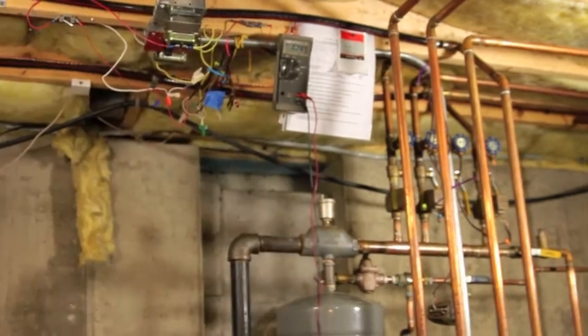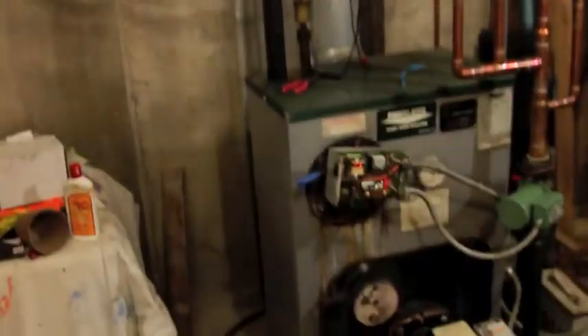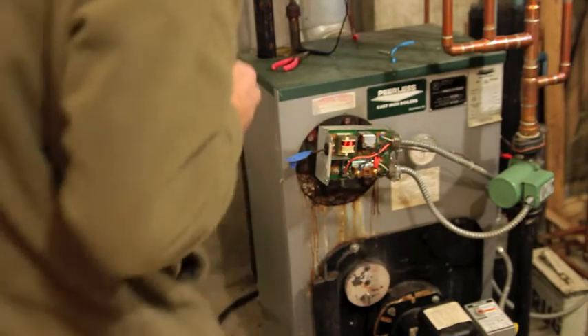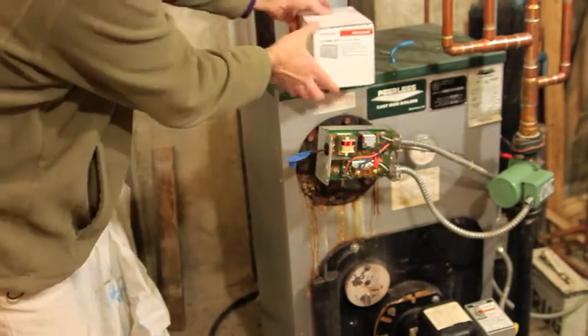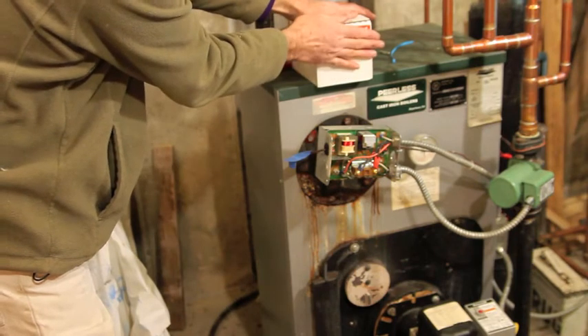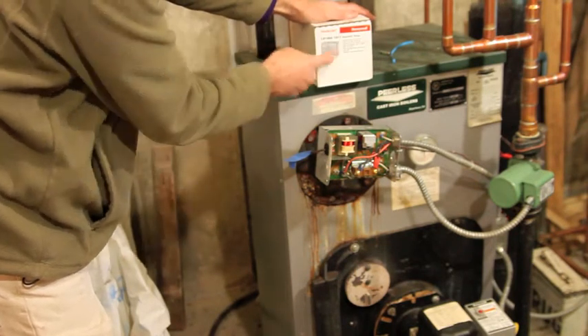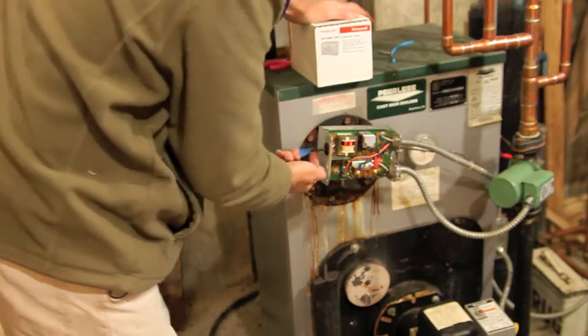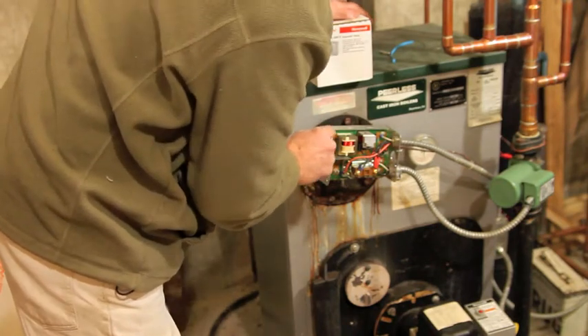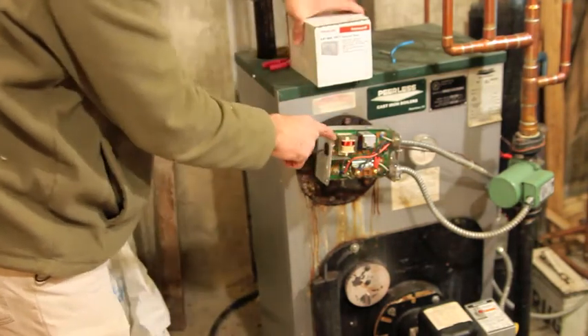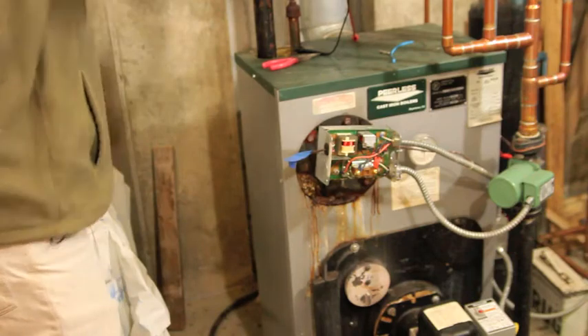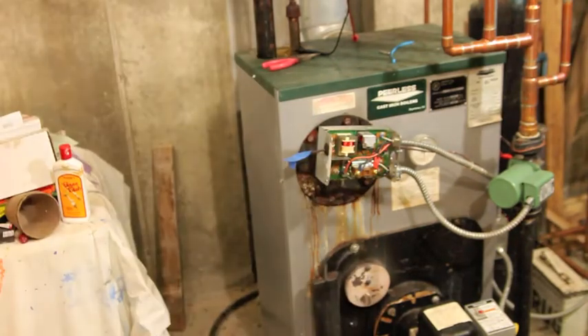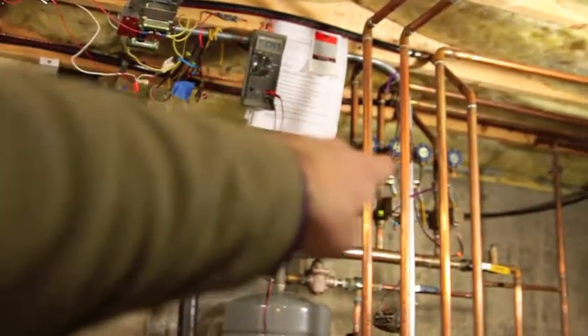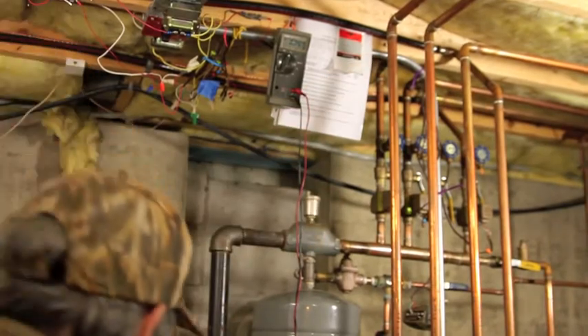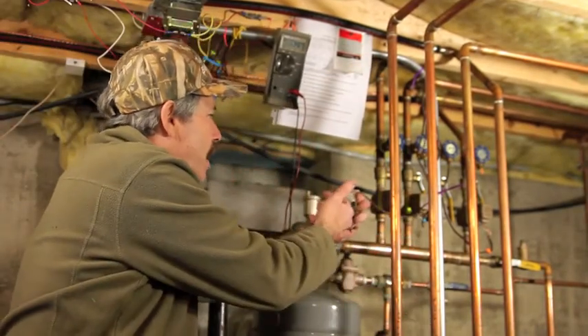aquastat. Let me bring that down, show you the aquastat. There's the aquastat. Also, for my family, we have a spare aquastat right here. In case I'm not around and something goes wrong, don't let them sell you another one. Spare one right here. Same thing. 2 pins on the left, 2 Taco valve, and it says right there, thermostat, T and T. It's white and red. And it goes back to each one of the Taco valves. Each Taco valve comes in and is all tied together.